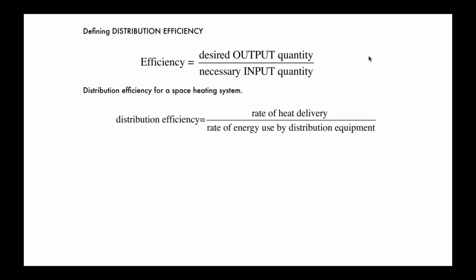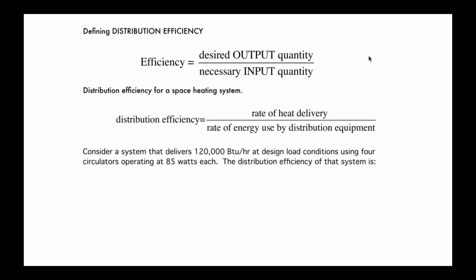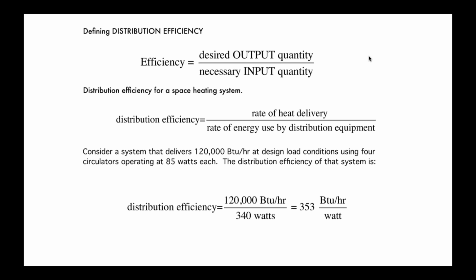So we're going to define distribution efficiency as a rate of heat delivery in BTUs per hour divided by the rate of energy use by the distribution equipment. That would be one or more circulators in a hydronic system, or typically a blower fan in a forced air system. So here's a quick example. Say we have a hydronic system. Under design load, it can deliver 120,000 BTUs per hour. And we've got 4 standard permanent split capacitor motor wet rotor circulators at 85 watts that have to run to deliver that 120,000 BTUs per hour. So really simple. You just take the rate of heat delivery and you divide it by the total watts that is necessary to make that heat delivery.